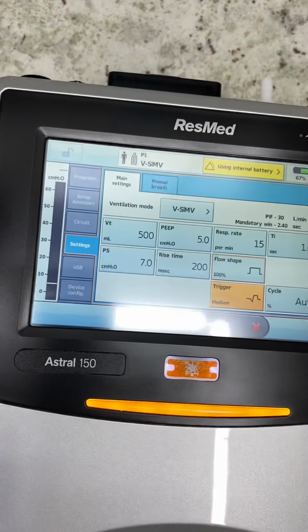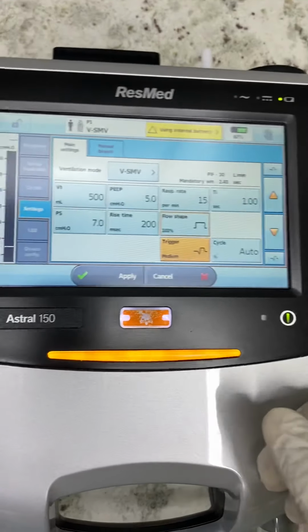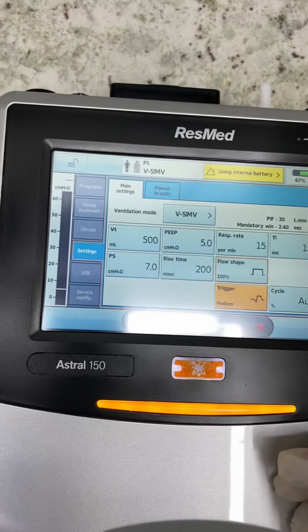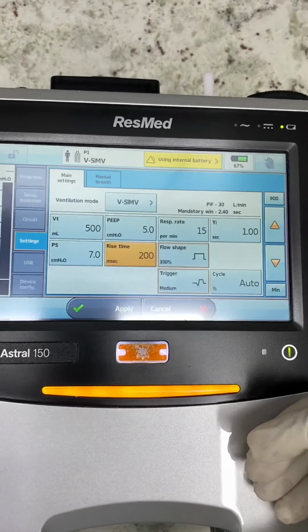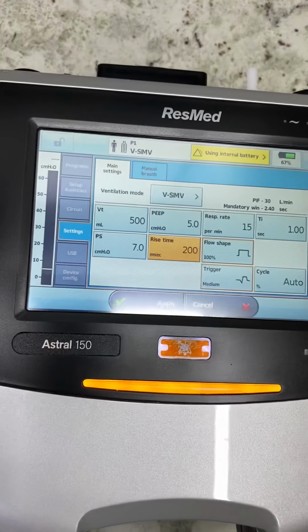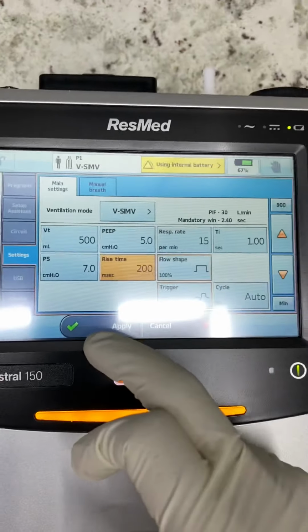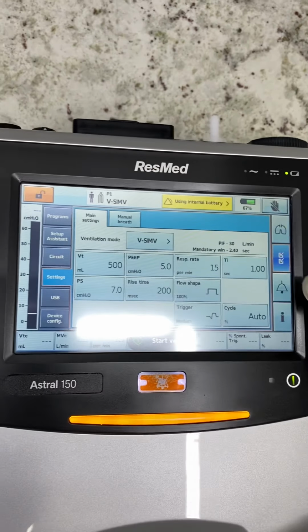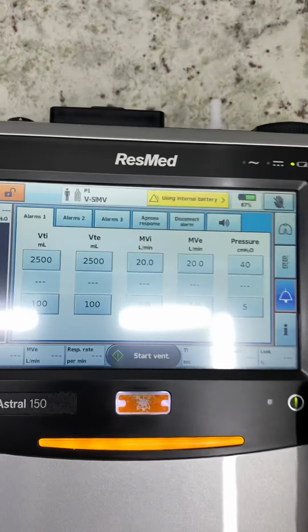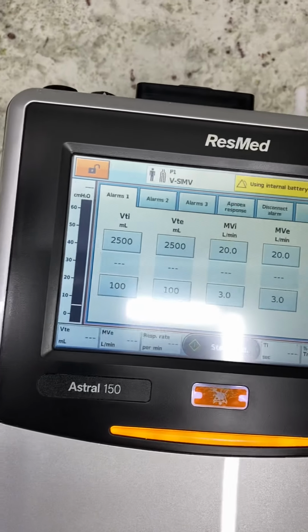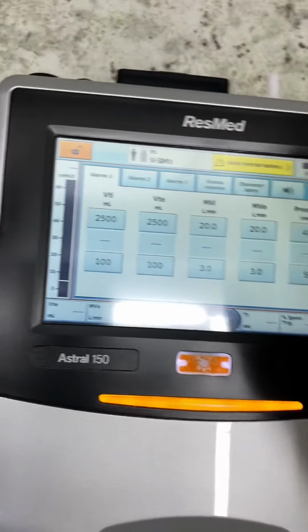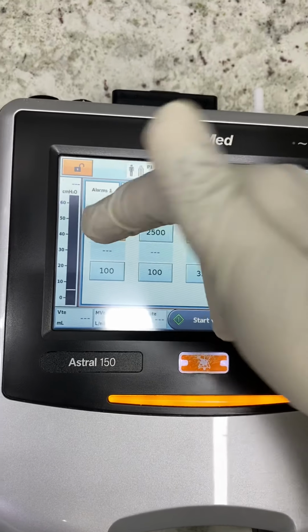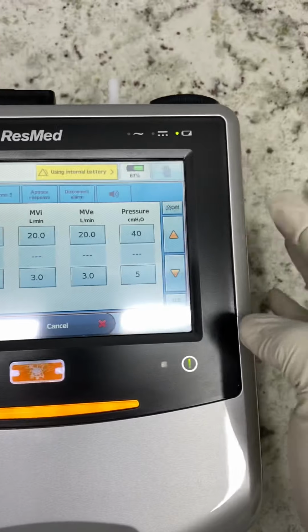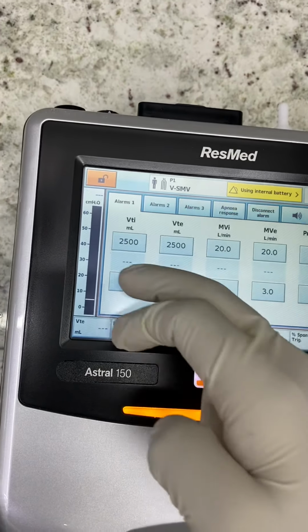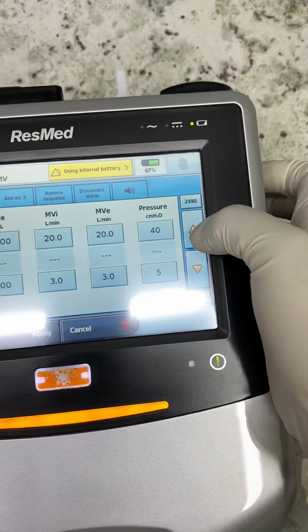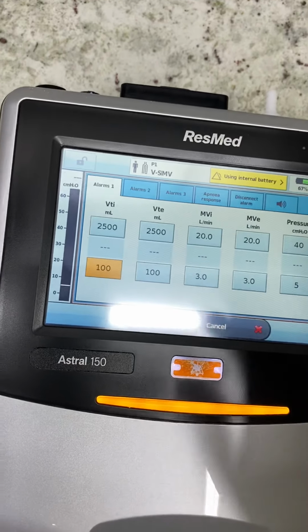And rise time is how fast it should reach the peak pressure. So it's like a ramp or whatever is the rise time. You can choose it, the default is 200 milliseconds, then check the flow pattern and you can change it if you want. Then once you set up everything, you can apply it. Then go to the alarms, where you have the alarm limits, tidal volume, everything, alarm 2, 3, many alarms. For each alarm, you can press it up, higher limit the same way by pressing the arrow up and down, then apply it. Lower limit the same way, arrow up and down, then once you reach the desired level, apply it.